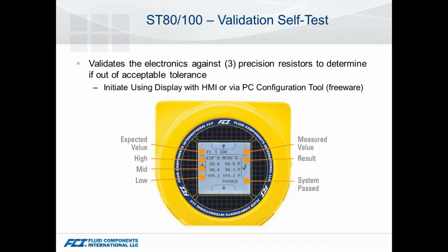With the product, if you've got the HMI, you can initiate the self-test in the field without hooking anything up to it. You don't even have to open up the enclosure. Those optical interfaces can be accessed through the glass itself. If you've got the ST80 without the buttons, there's a PC software configuration tool that we provide that allows you to run that test on demand, or you can schedule these tests on either version to occur at a certain point, daily, weekly, or monthly, depending upon your needs.